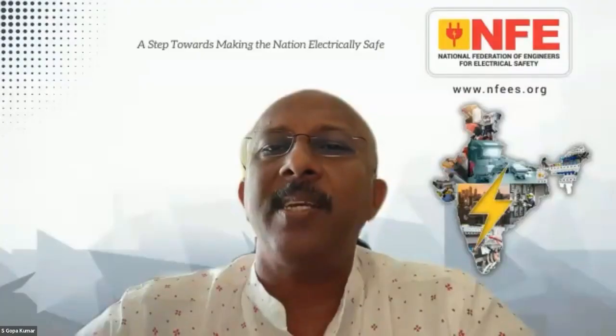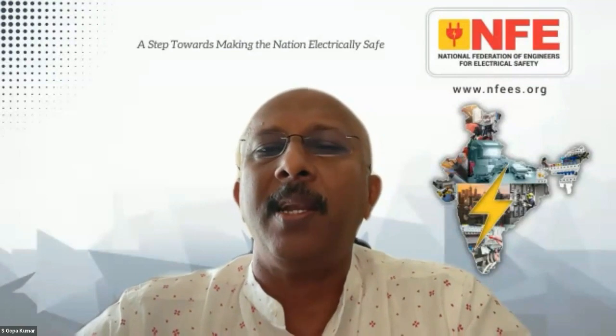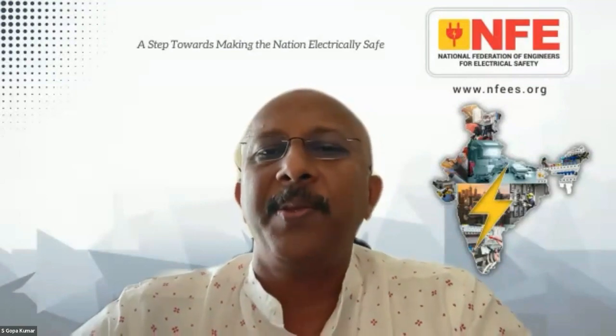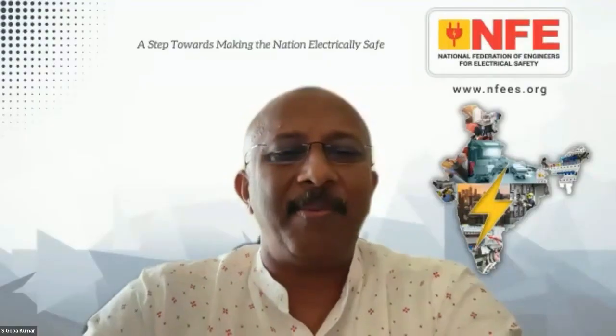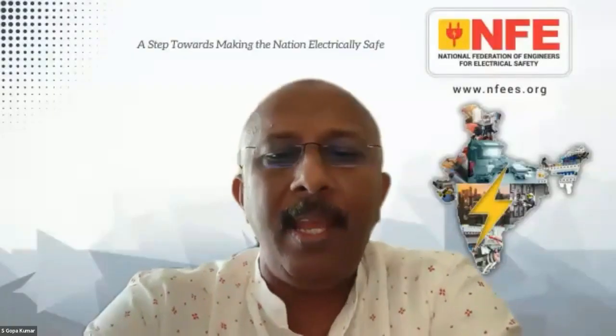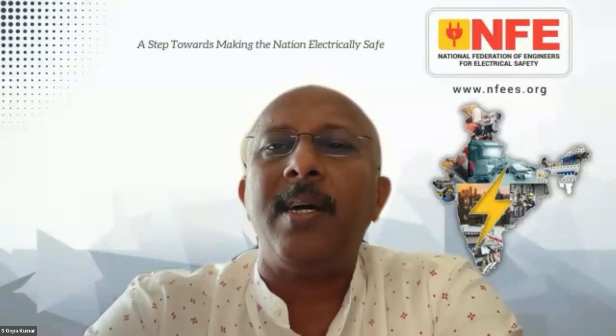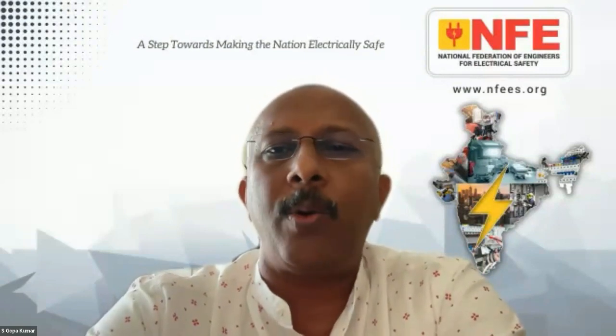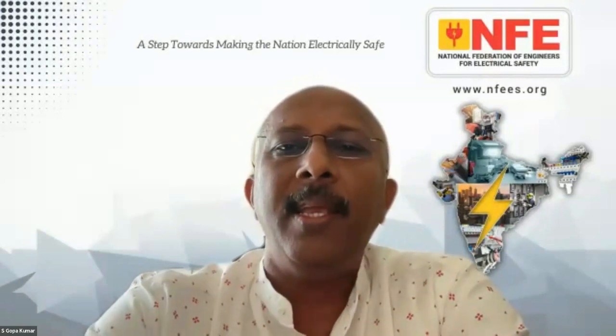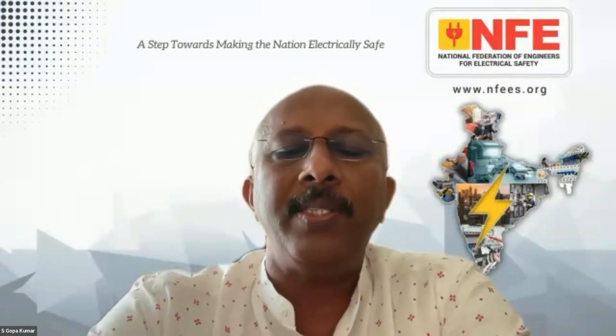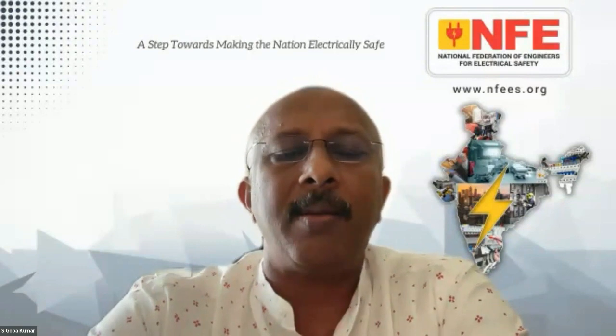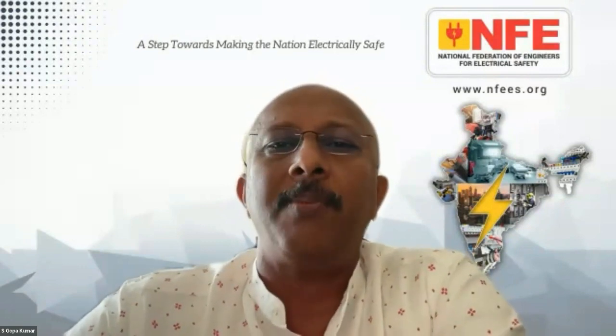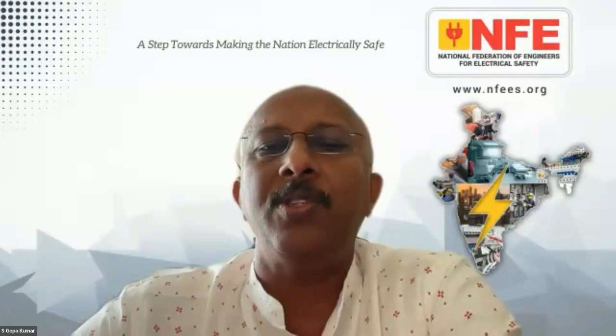Yes. Now there is a question: what is the difference between earth conductor and PE conductor? The definition which is given: the earth conductor means any connection from the MET to a buried earth electrode, and anything which is running along with the phase and neutral conductor is a protective earth conductor, because the protective earth conductor is supposed to carry a substantial amount of fault current. So the sizing is very important.